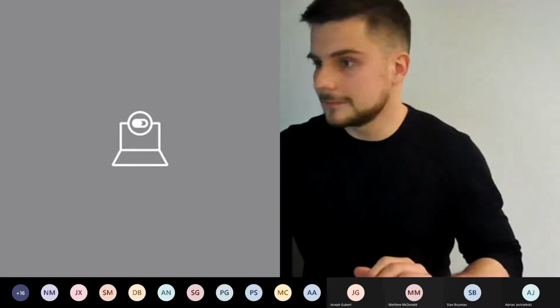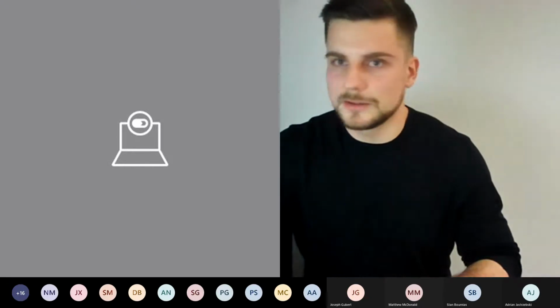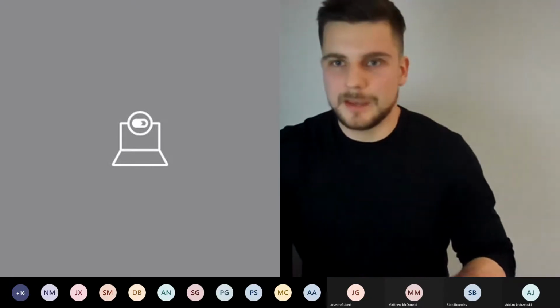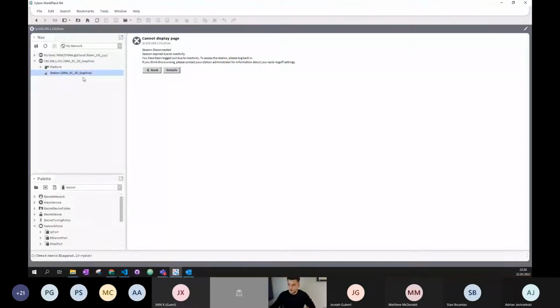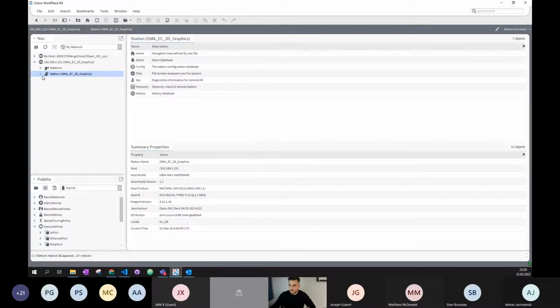Okay, so right now I'm going to switch to my screen, and we will do some practical work. I'm going to connect to the Niagara, and I'm going to enable the station in which I'm going to configure and integrate the I/O modules. As you can see here on the left side, this is my Mach36, and in the Mach36, I have a running station. So this is my starting point.